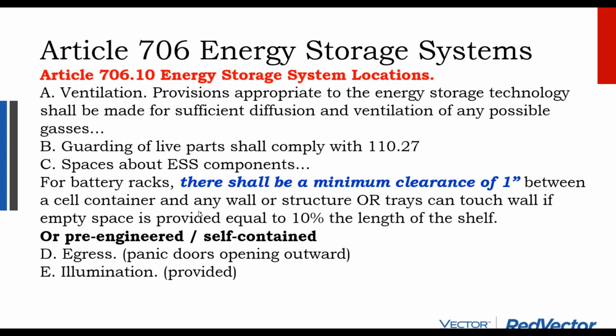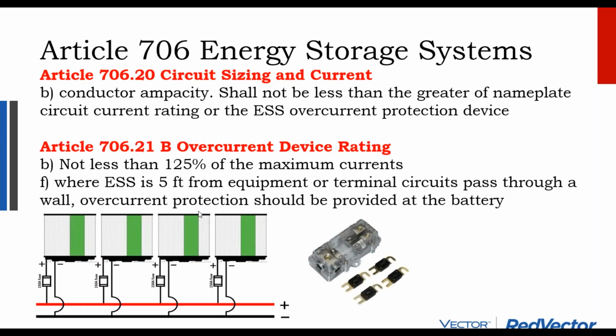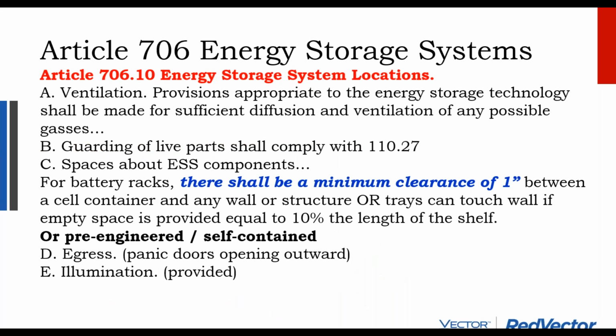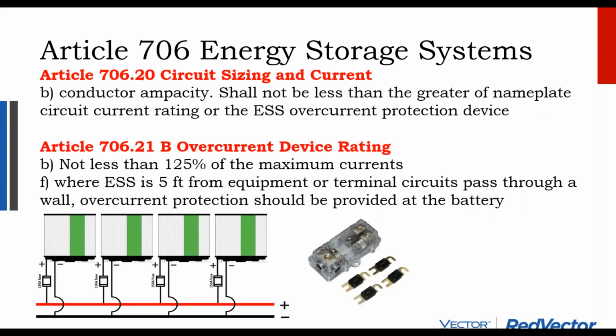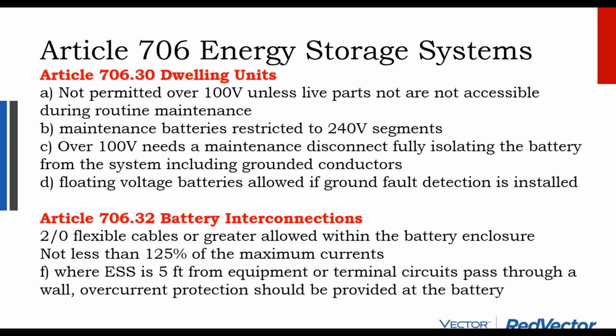A lot of these requirements are exactly the same as what we talked about in Section 480. They're just repeats. 1 inch of clearance between the batteries and the wall. You are allowed to have the shelf of the batteries connected to the wall. It has to either be a pre-engineered system like the Tesla Powerwall, or additional space between the wall and the battery is required if the batteries are connected to a shelf that's connected to the wall. And that's the main thing to know: when you get into higher voltage systems, you start to be required to put overcurrent protection into the circuits, and you get into more spacing requirements as well.